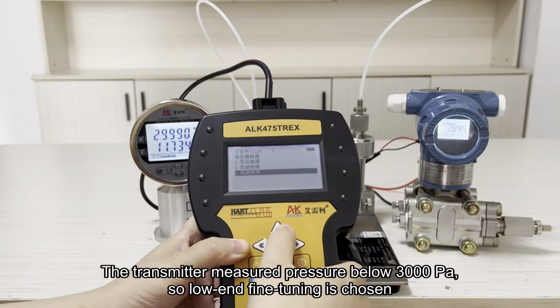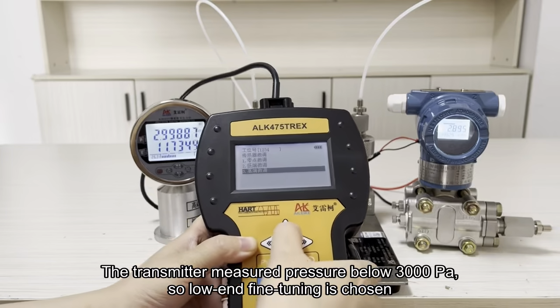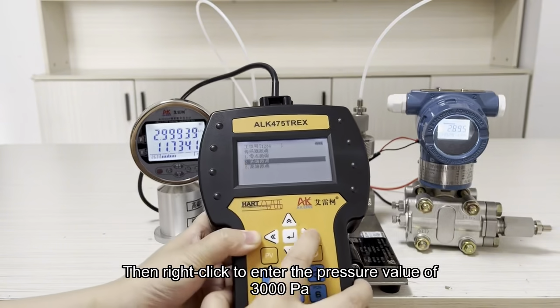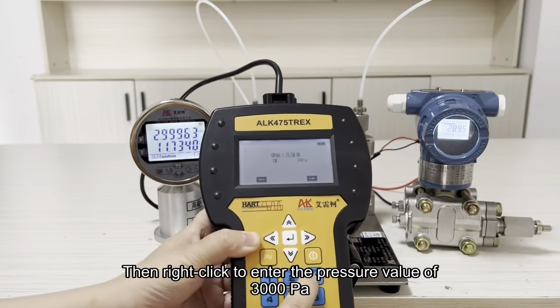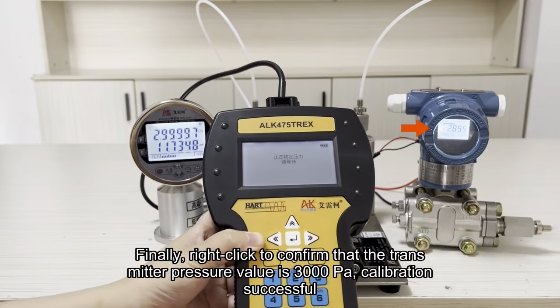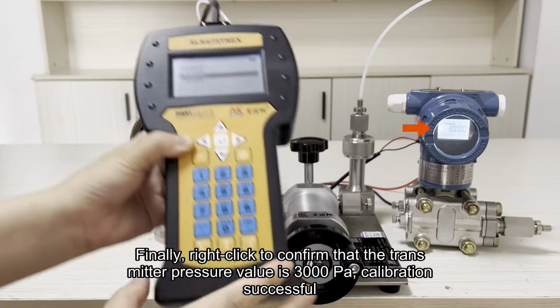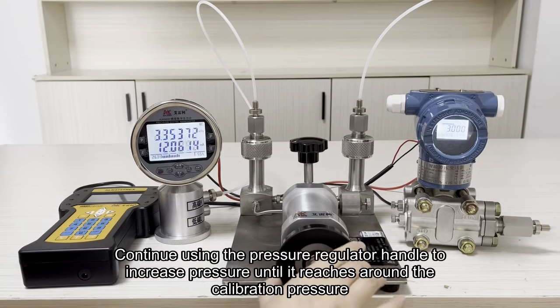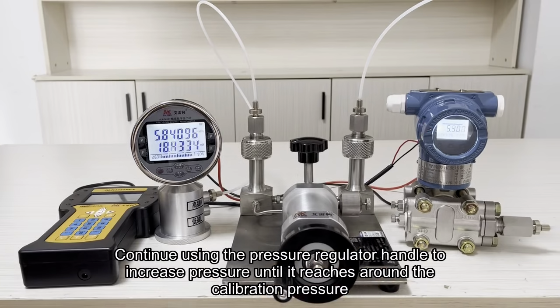The transmitter measured pressure below 3000 Pa, so low-end fine-tuning is chosen. Then right-click to enter the pressure value of 3000 Pa. Finally, right-click to confirm that the transmitter pressure value is 3000 Pa. Calibration successful. Continue using the pressure regulator handle to increase pressure until it reaches around the calibration pressure.